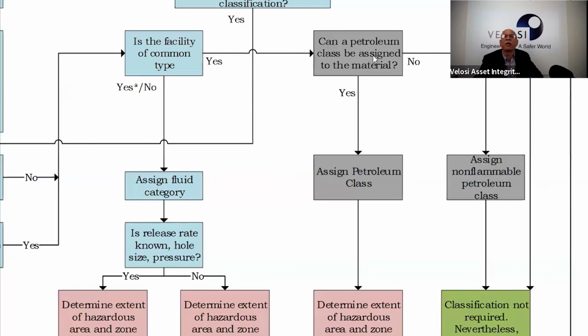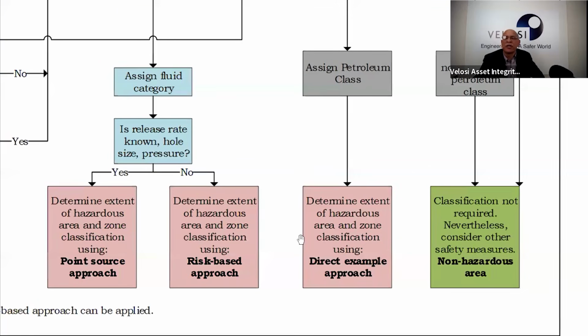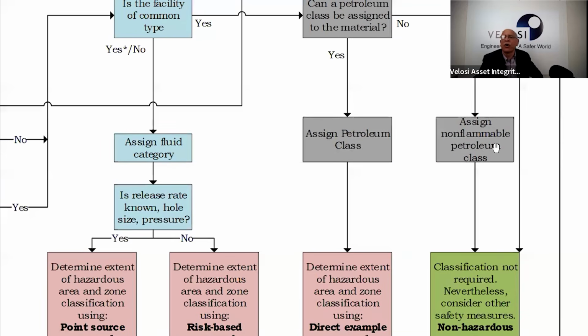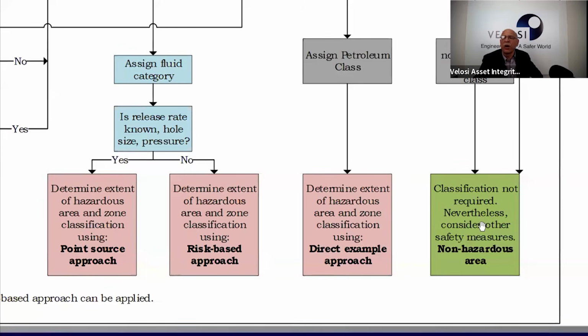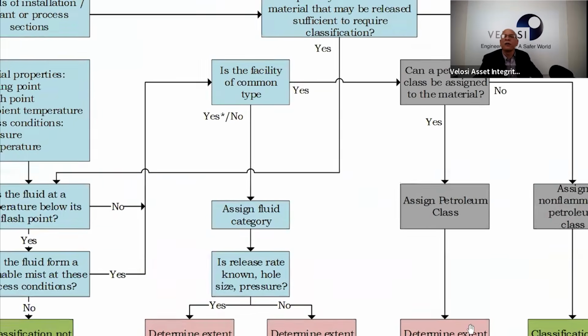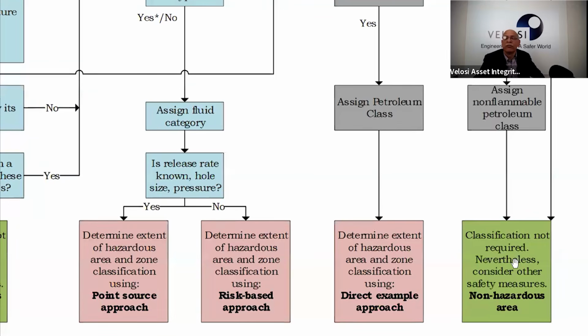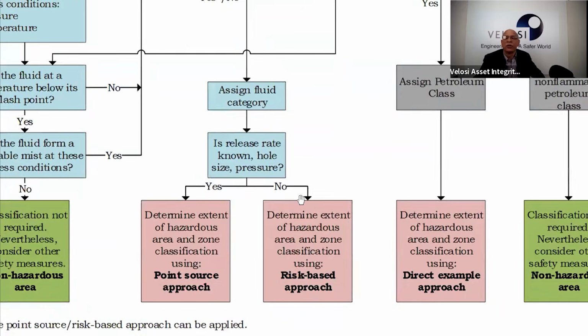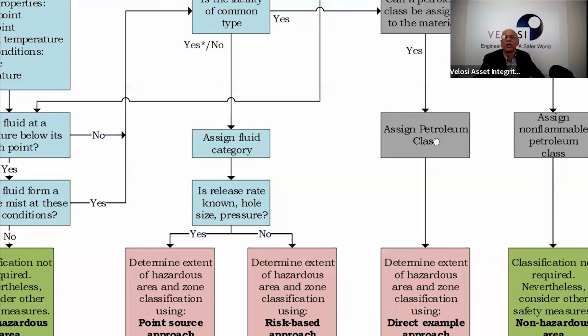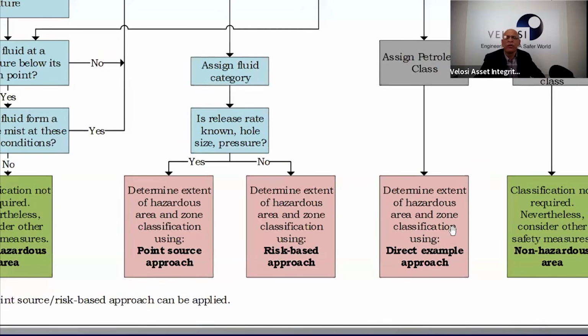Then, can a petroleum class be assigned to the material? If yes, then we assign a petroleum class and determine the extent of the hazardous area and zone classification using the direct example approach. If we know the petroleum class, we can apply this. Normally, we follow a combination of the direct example approach and the point source approach. The risk-based approach is normally not followed because it is qualitative, and a qualitative risk approach may misguide you, but it can also be used.